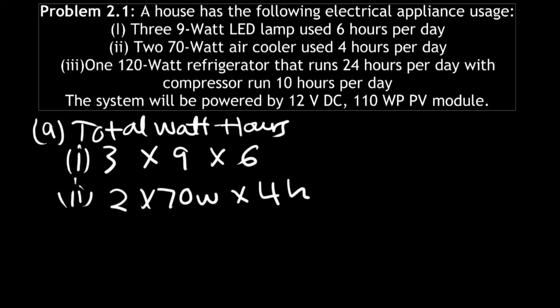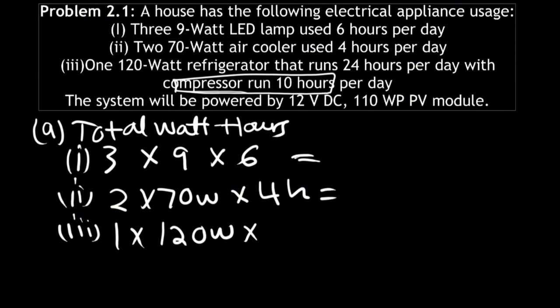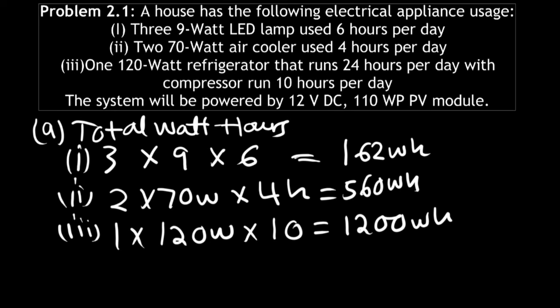For the third appliance we do the same. We have one 120-watt refrigerator that runs 24 hours per day, but the compressor runs only 10 hours. So we take the compressor hours only: one times 120 multiplied by 10, giving 1200 watt hours. The air cooler gives 560 watt hours and the LED lamps give 162 watt hours. Now we add these watt hours to get a total.